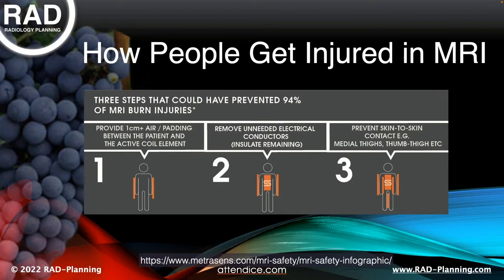And depending on the specific frequency of the RF transmitters, which is a function of field strength, and depending on the position of the RF body coil transmitters behind the plastic covers in the bore, that distance may be, as I say, 5 millimeters, it may be a centimeter. It doesn't have to be a whole lot of space, but if you get into that standoff distance volume, the RF energy can essentially excite. What we think happens is that it excites the water-fat boundary below subdermal fat. Now, you have no temperature or pain sensors in subdermal fat, and you have none in the musculature below. So we can effectively cook you without you having any sensation in the moment.